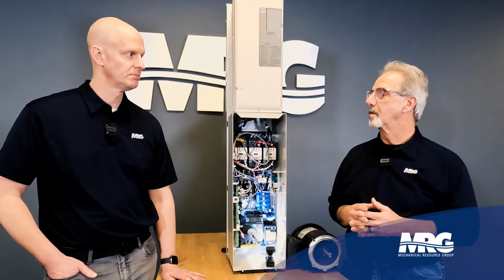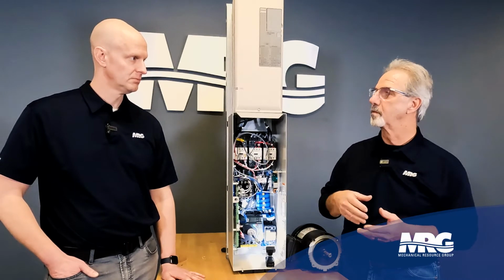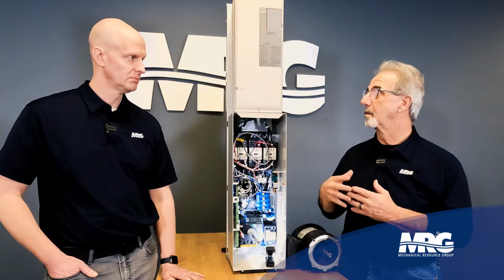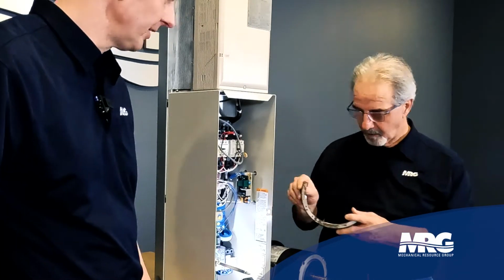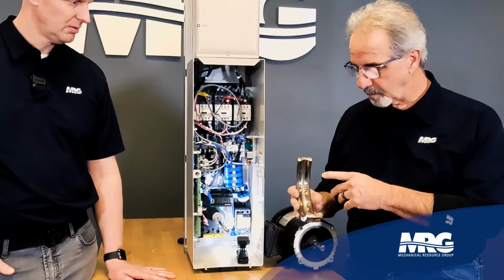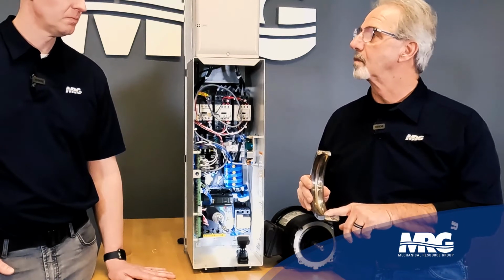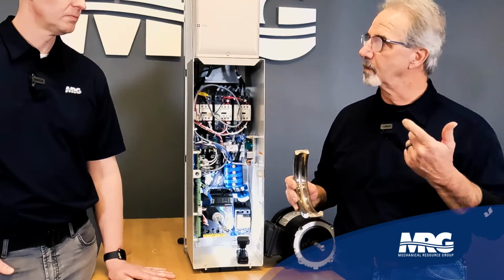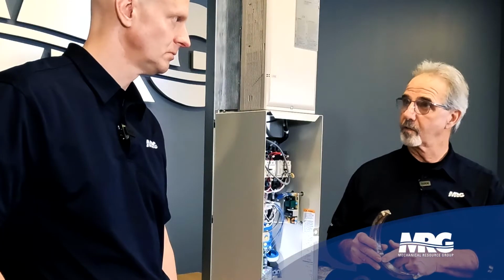Okay. It seeks that ground source, and as it enters the magnetic field, it goes out through the bearings, and it creates a pattern in the outer races of our bearings. It starts out as a frosting, what they call either frosting or railroad tracking. You have an example of a bearing that we have? Right. If you take a look at this, on the outer race the balls are supposed to run on a machined surface. As that voltage begins to traverse from the inner race through the ball to the outer race, it creates that frosting pattern, and over time it will become what we call pitting. It almost looks like a railroad track.